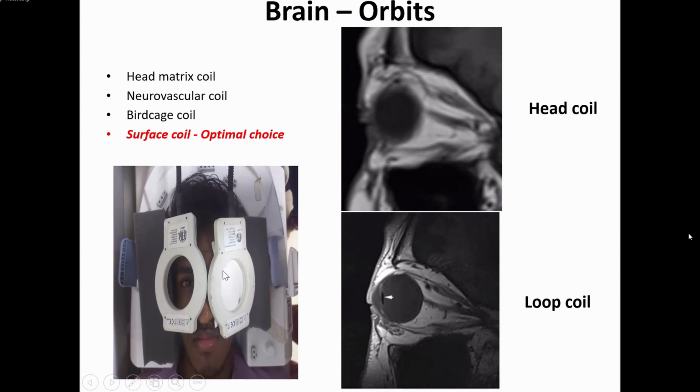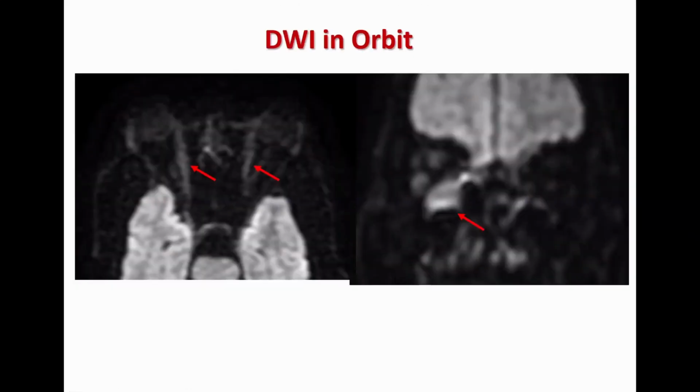You get high resolution images and you get high SNR. The coil in close proximity to the eyes will strengthen the MR signals. Okay, localized sensitivity will ensure that the noise from outside the imaging area will be significantly reduced, and there won't be any wraparound artifacts even with a shorter FOV. And you all know when you use a volume coil, definitely the sensitivity will decrease with increasing distance from the coil, right? And for orbits, you have several indications where they ask for MRI orbits or optic neuritis.